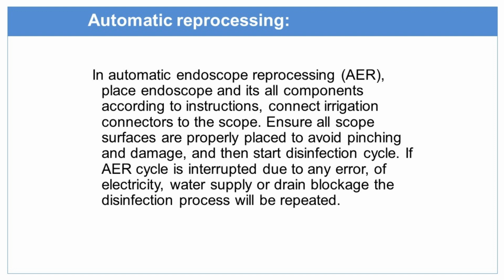Automatic processing. How do we do the automatic processing? Place the endoscope and all its components according to instructions. Connect the irrigation connector to the scope. Ensure all of the scope's surfaces are properly placed to avoid pinching and damage. Then start the disinfection cycle. If the cycle is interrupted due to any error, electricity or water supply failure, or drain blockage, the disinfection process will be repeated. So make sure that when you are working with automated reprocessing, your scopes are going through the reprocessing mechanism.